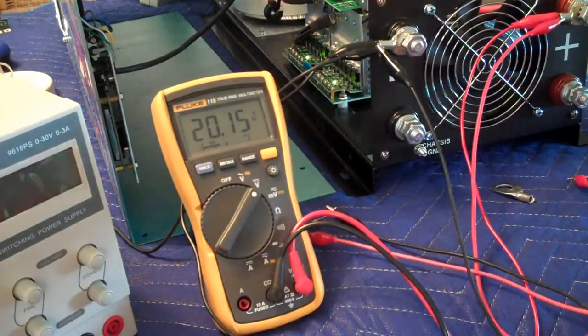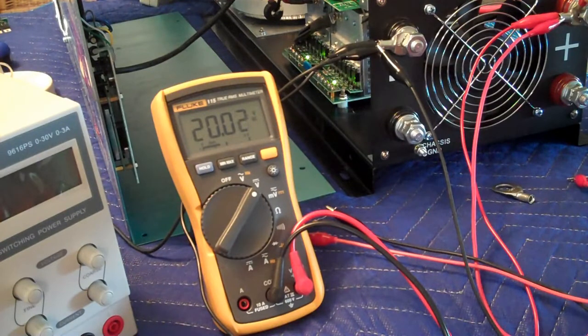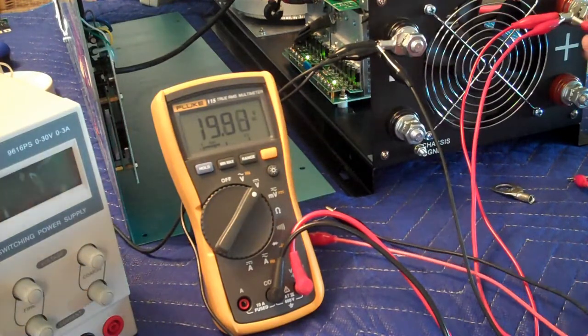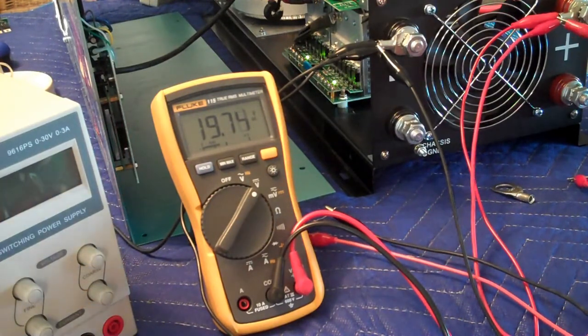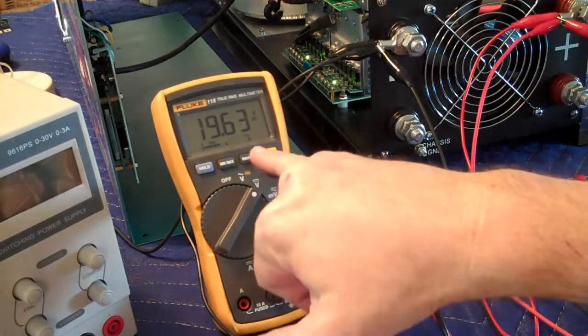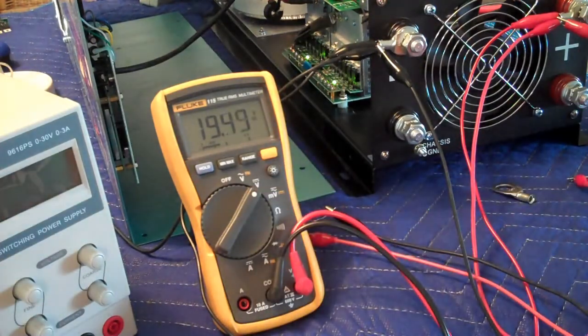And then you can attach that across the terminals here, and that will cause the power to bleed off into that resistor. And so you can see here it's starting to go down a little bit faster than before, but it's still taking a decent amount of time. So you need to test the voltage on these terminals, make sure it's down at a pretty low level, you know, less than a volt or so, before you start messing around inside of it.